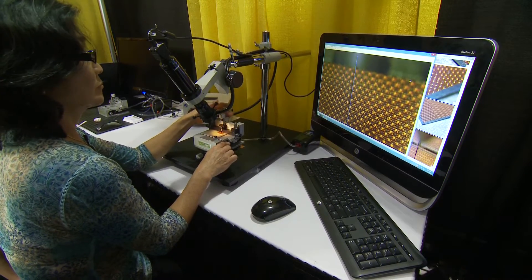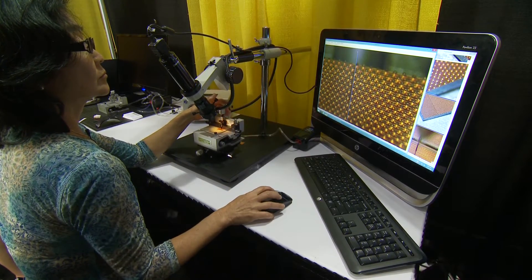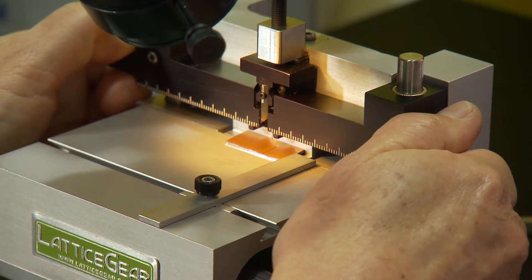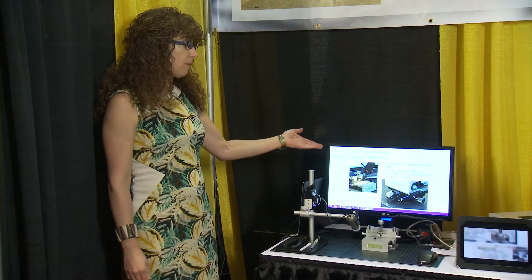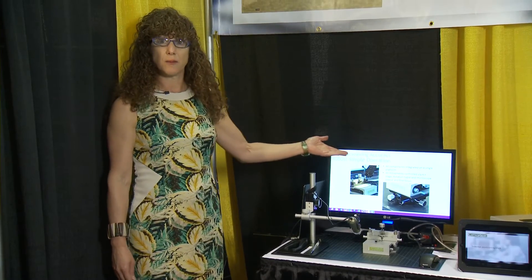The LatticeAx 300 has a high-accuracy vision package supported by a robust setup and XYR sample positioning stage. The LatticeAx 300 is capable of 10 micron cleaving accuracy with a robust, simple operation.